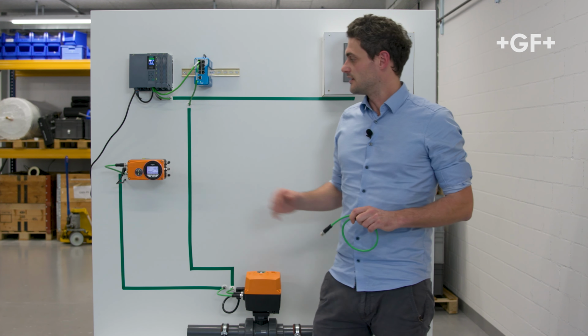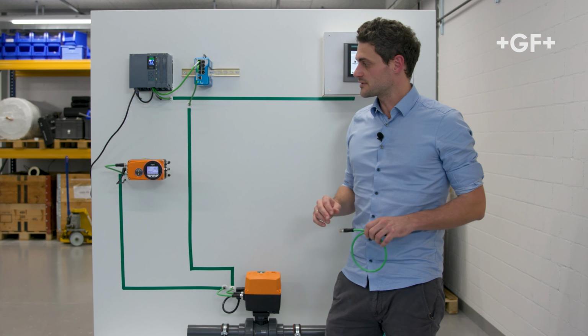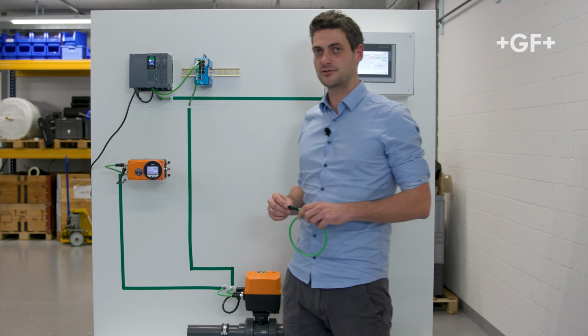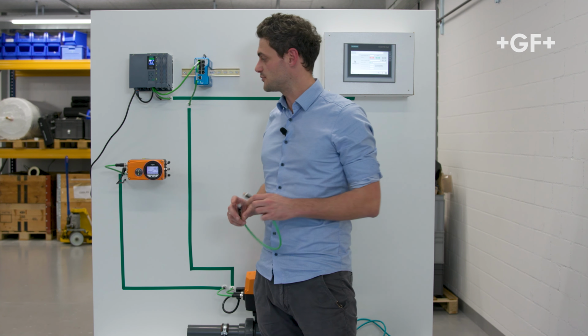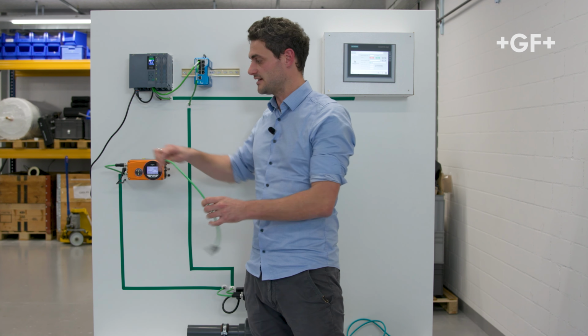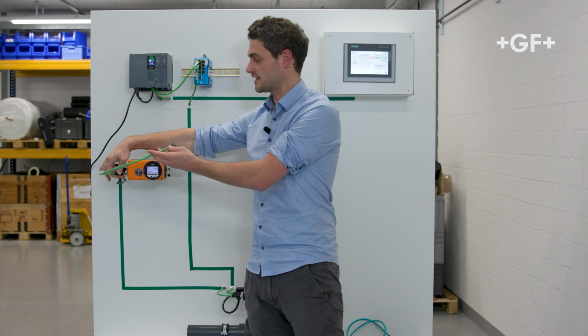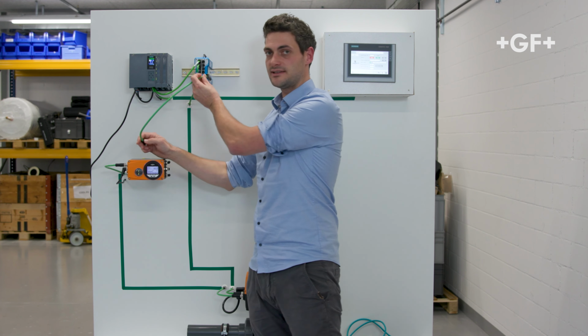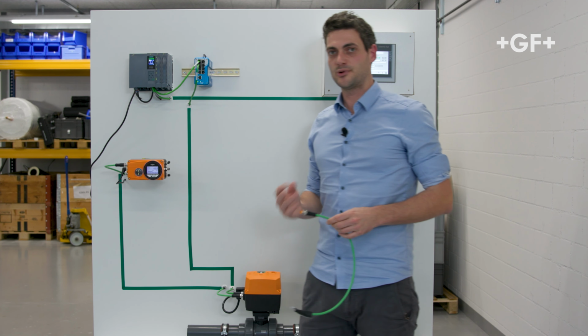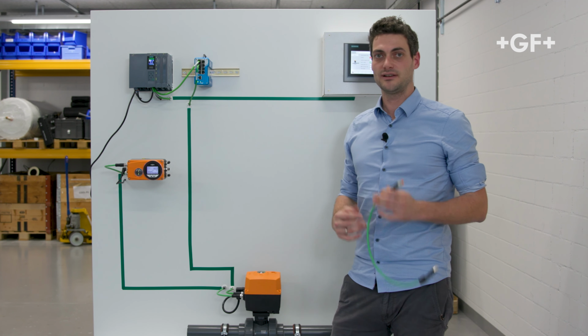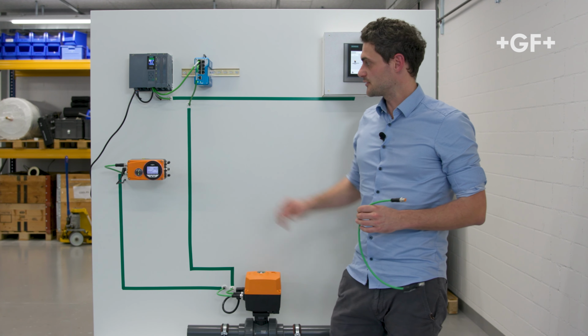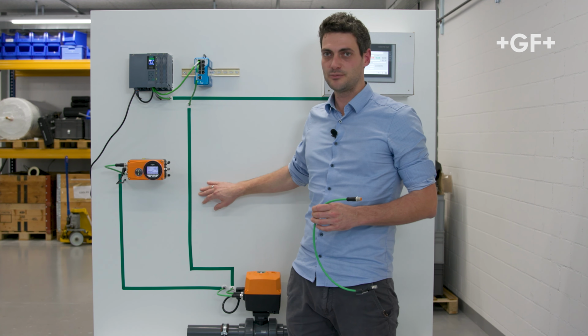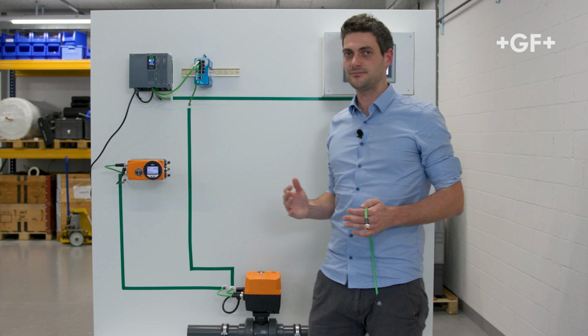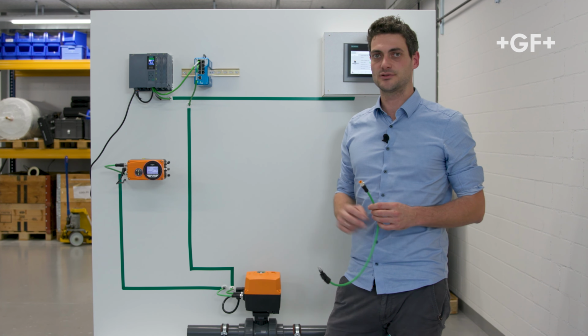With Profinet, it's even possible to close the ring, so to create such a redundancy ring, which means going from the last device in the line, via the second port in this example, back to the Ethernet switch. This is a very important feature in terms of high availability of a process plant, because if one cable breaks in between of this line, this doesn't matter. The communication just goes the other way around.